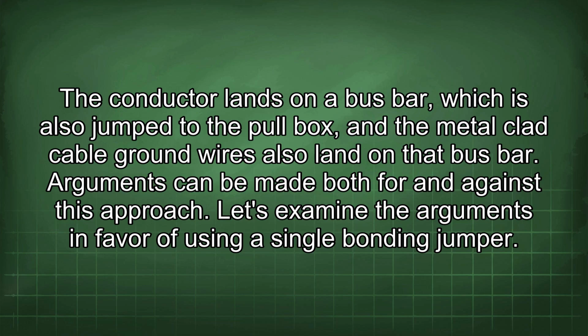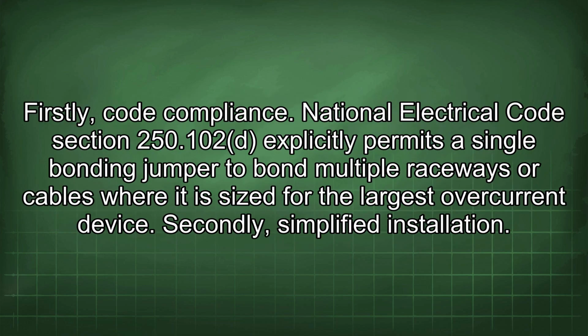Let's examine the arguments in favor of using a single bonding jumper. Firstly, code compliance. National Electrical Code Section 250.102 explicitly permits a single bonding jumper to bond multiple raceways or cables where it is sized for the largest overcurrent device.